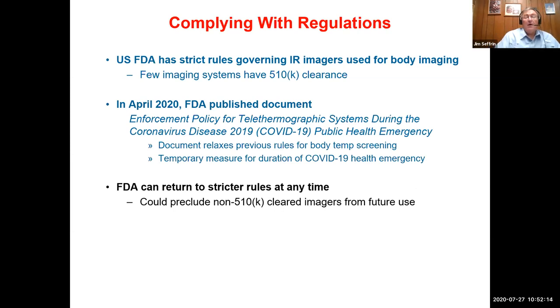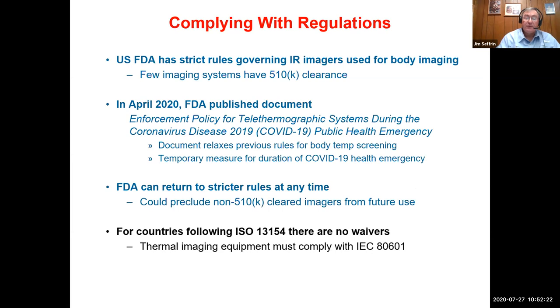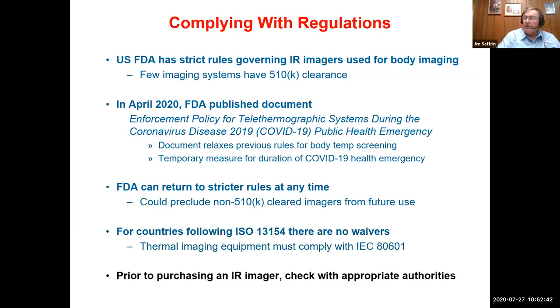We don't know. If they do that, it could preclude non-510K cleared imagers from being used in this application in the future. For countries following ISO 13154, there are no waivers or exemptions. Thermal imaging equipment must comply with the requirements laid out in ISO 13154 and the document that it incorporates by reference, the International Electrotechnical Commission 80601. Prior to purchasing an imager, make sure you check with appropriate authorities if this is an application that you want to become involved with for the instrument's compliance with regulations.